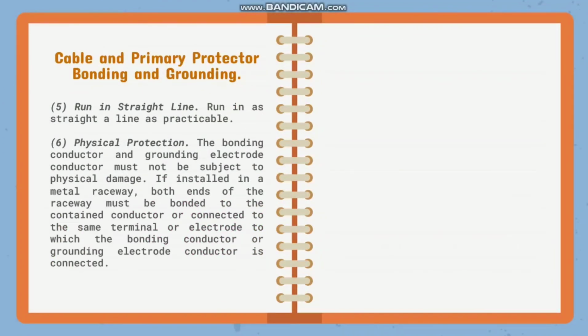So, next, run in straight line. Run in a straight line as practicable. So, ang reason po for this is because lightning doesn't like to travel around corners or through loops, which is why the grounding electrode conductor or bonding jumper must be run as straight as practicable.